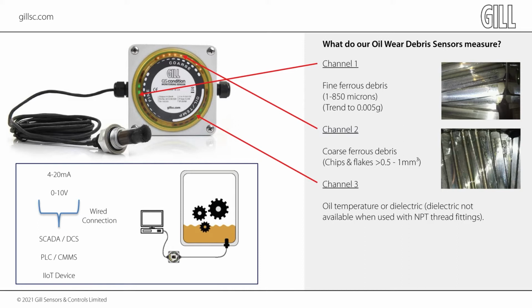Results from the sensor can be monitored either by regularly noting the number and color of LEDs illuminated on the display panel, or by connecting the sensor to a PLC, SCADA, IoT device, or DCS and trending the fine wear rate through third-party software. Once connected and powered, the WearDetect sensor can be tested by using a Gill debris strip.